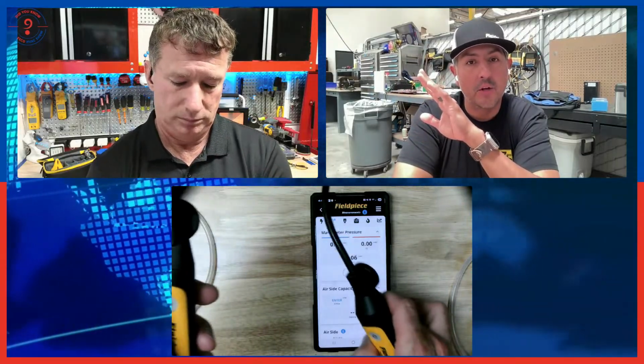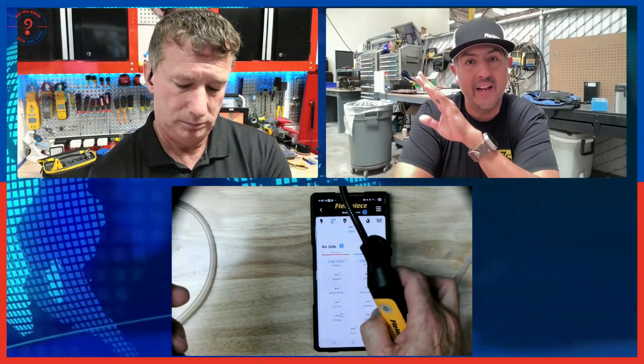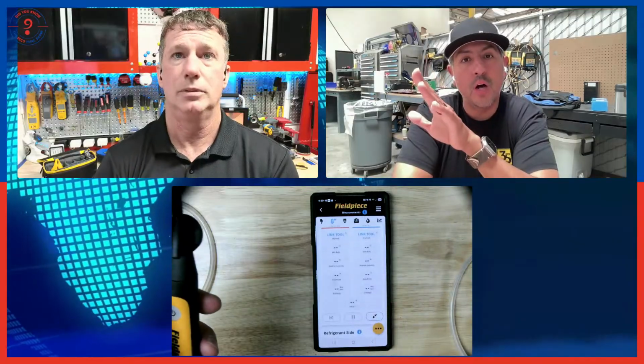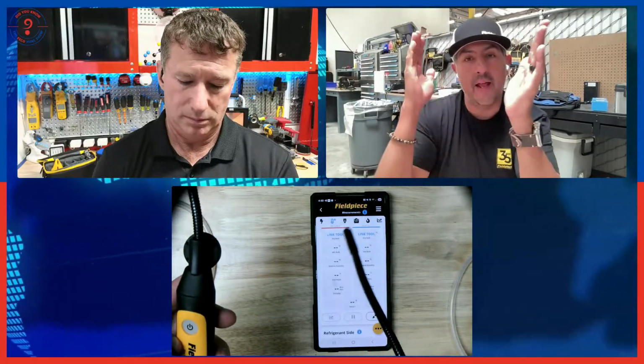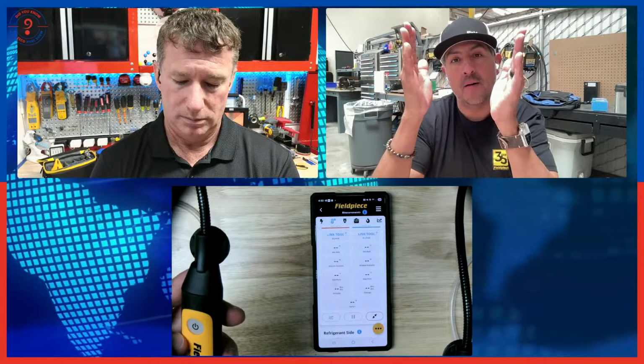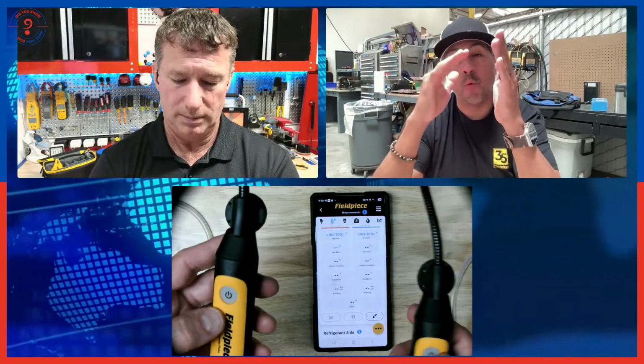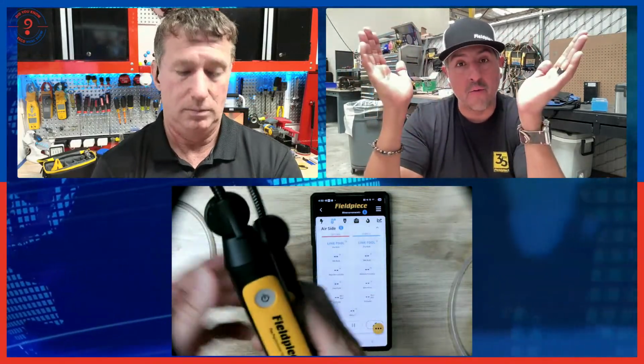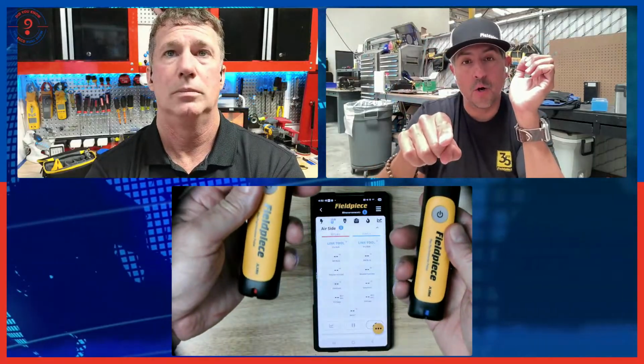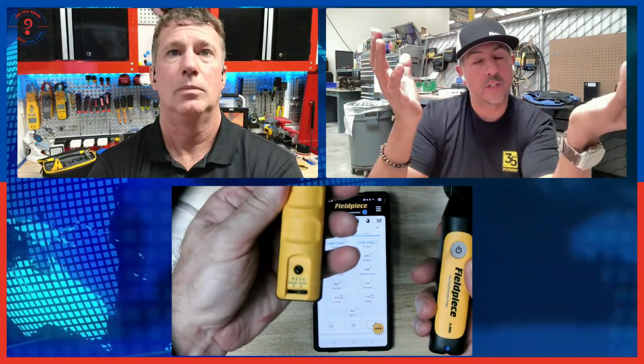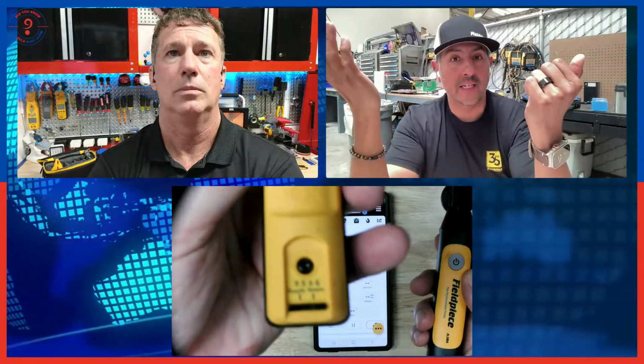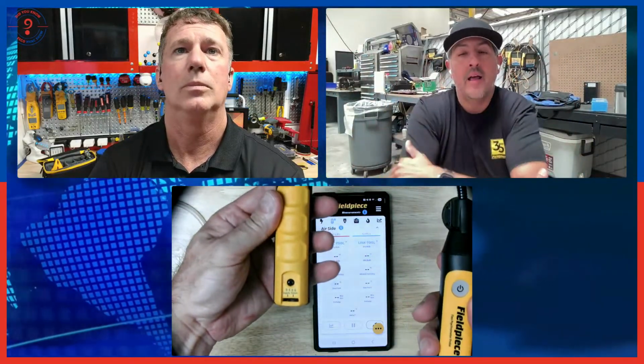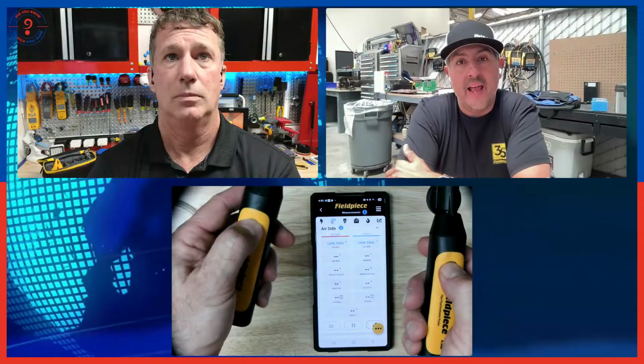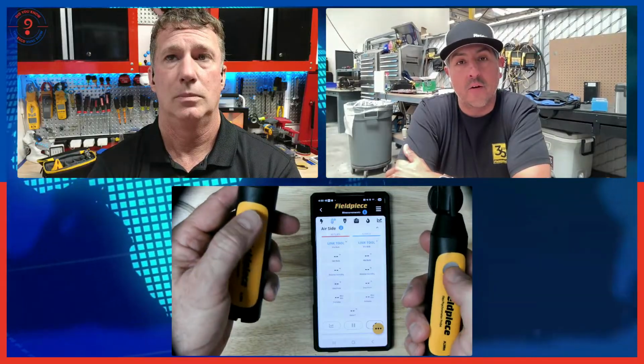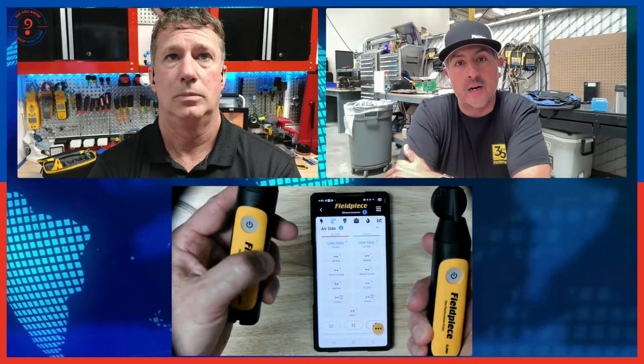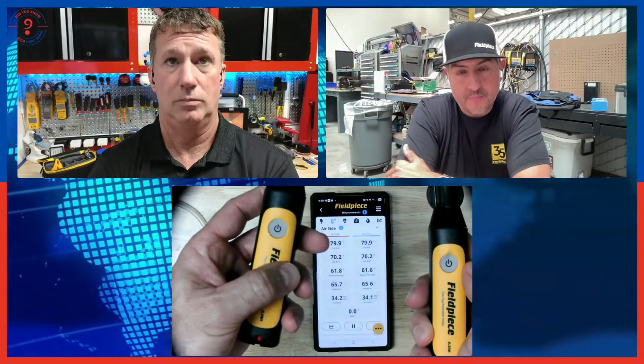If you scroll down a bit, you'll see where it says air side, with a red return column and a blue topped supply column. We link these the same way. On the back of those probes there's a switch, one side says return, the other says supply. You power them on and the app knows which is which, and if you've already synced or linked them, they'll automatically display there.